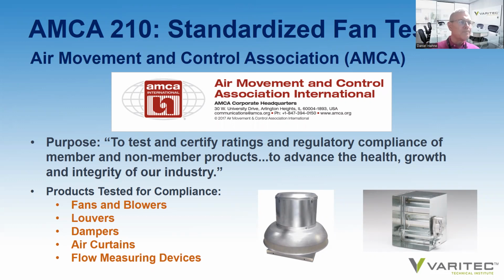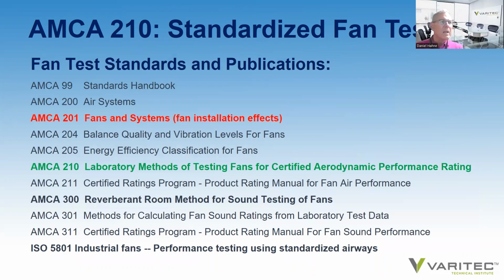For fans, AMCA has published a number of standards. The 2 standards we're going to focus on today are AMCA 210 for laboratory methods of testing fans for certified aerodynamic performance, and AMCA 201 on fans and systems, and how installed fans can result in system effect and how to calculate that effect using the standard.